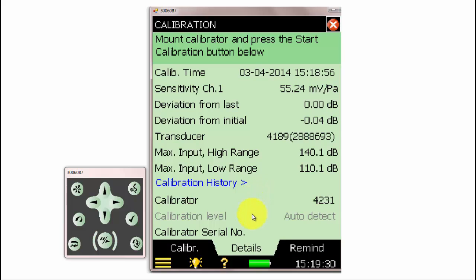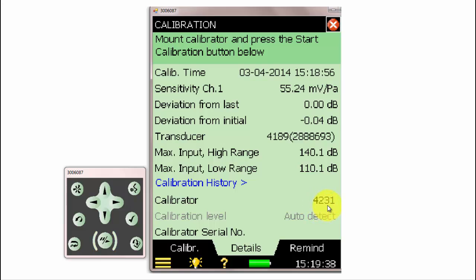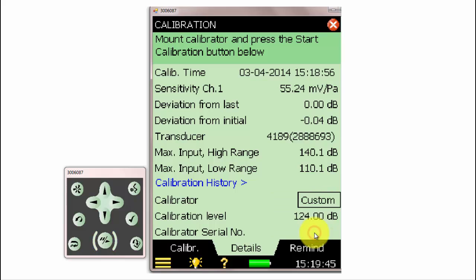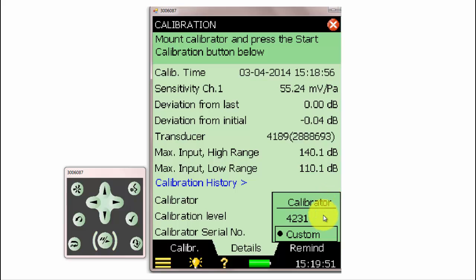Under the Details tab, we can also select what kind of calibrator we are using. The default microphone calibrator is a type 4231, which will output 94 dB at 1 kHz. If we are using a different calibrator, we can select Custom Calibrator and input the calibration level of that custom calibrator.